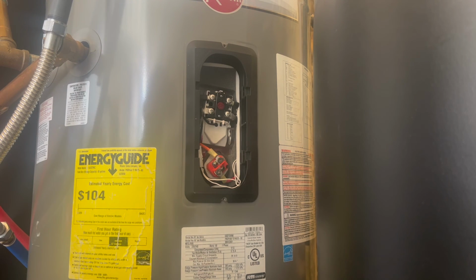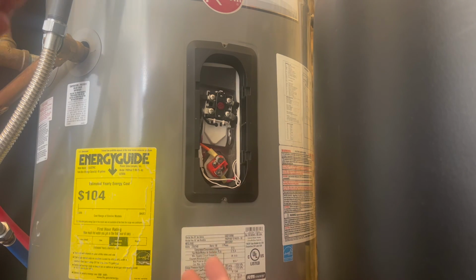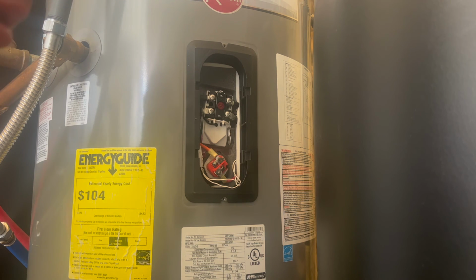A lot of times what I see is you put your hand, you know it's ambient temperature, let's just make up a number, say it's 85. Compressor's running and that fan is blowing nice cool air, right? If it's 85 degrees, that fan could be blowing 65 degree air through there. And that heat exchanger could be at 65 degrees. Excuse me. But when you go into test mode, the sensor for the heat exchanger says 90 degrees or 85. It's matching the ambient. Or it could say 240 or negative 40, and that's just a problem right there. Boom, that thing gets replaced.